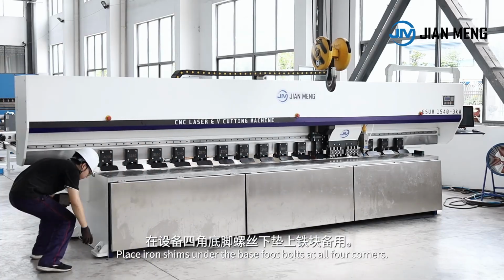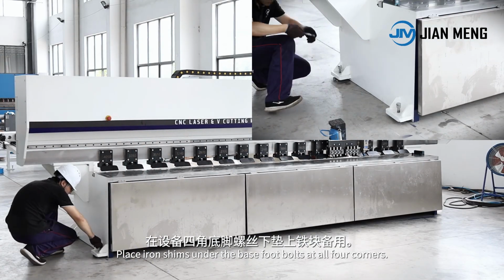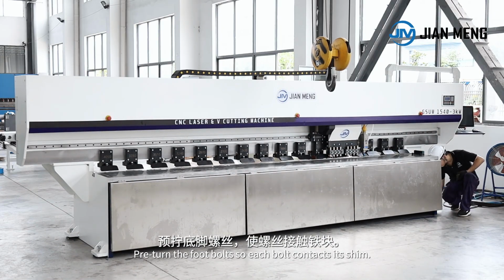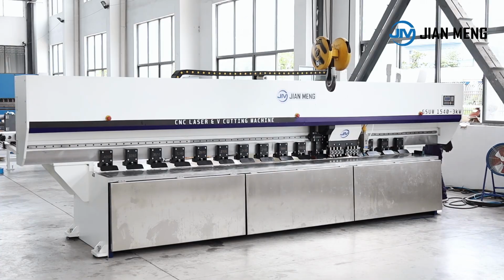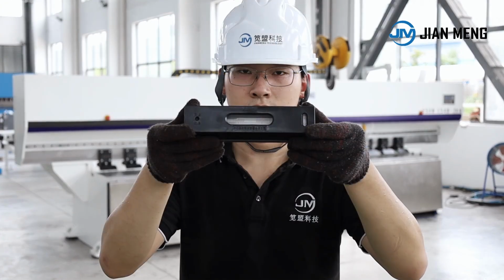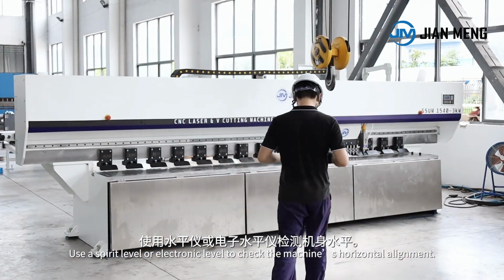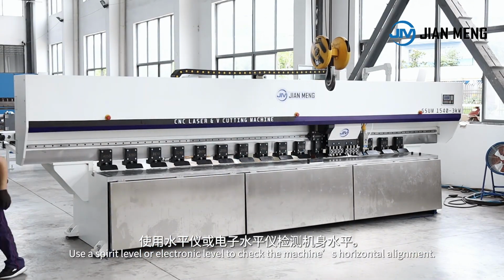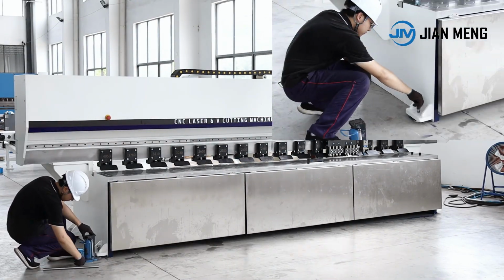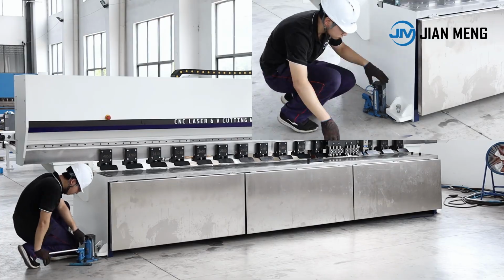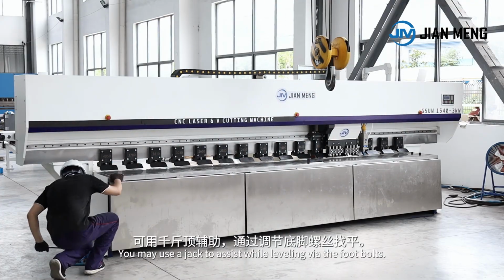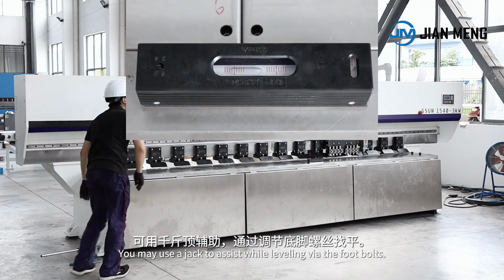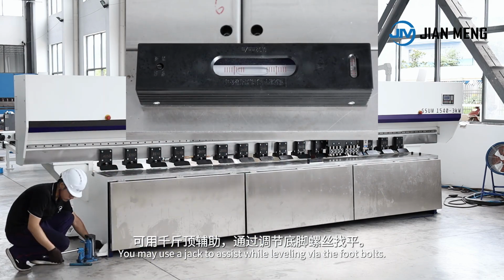Place iron shims under the base foot bolts at all 4 corners. Pre-turn the foot bolts so each bolt contacts its shim. Use a spirit level or electronic level to check the machine's horizontal alignment. You may use a jack to assist while leveling via the foot bolts.